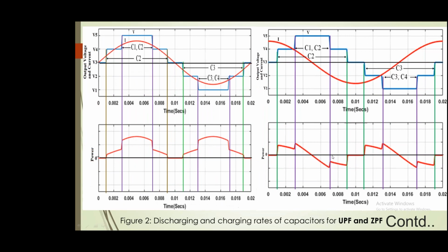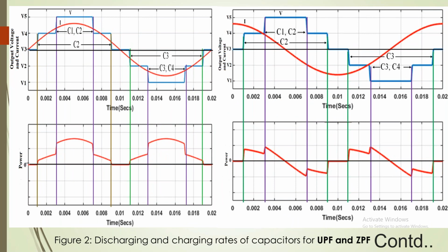So what happens is the inner capacitors still maintain the voltage. Whatever charge they discharge, they are also charged. So inner capacitors still maintain the voltage constant. Thereby, if you are supplying zero power factor load, the five levels are maintained intact because the capacitors are still charged. But if you are supplying any power factor load other than zero, the inner capacitors will slowly discharge to zero, and the entire voltage is shared among the outer two capacitors. Thereby, the five-level inverter comes to a three-level inverter.